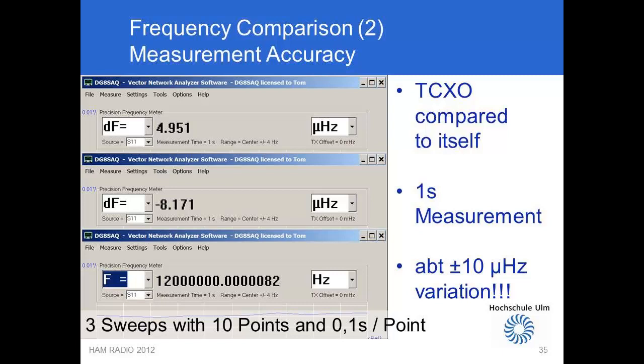On this slide I have investigated how accurate frequencies can be measured by measuring the phase during 1 second of the internal TCXO against itself. As the frequency difference shall be 0, it is the VNWA accuracy we measure, and by 3 repeated measurements I got a VNWA measurement accuracy of about plus minus 10 microhertz. To measure a frequency during 1 second to within 10 microhertz with conventional frequency counters is a very difficult task.